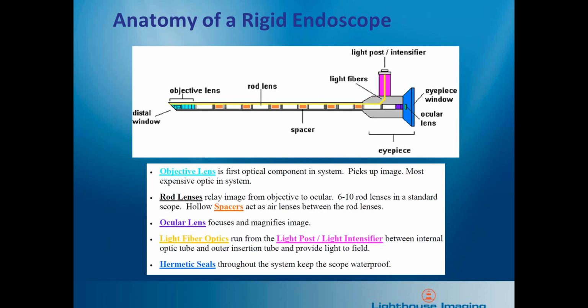So we'll see in the upper image here, starting at the left end of what's shown here, what would be typical for an arthroscope. We'll see the distal window, and then we'll have an objective lens assembly, which you could most typically think of as being like a camera lens. So that creates the image. And then inside of these rigid endoscopes are typically a series of rod lenses. This is a long, skinny piece of glass that transfers the image along the shaft of the endoscope. So in between these rod lenses would be hollow tube spacers. And then at the right end, or the proximal end, would again be this ocular lens and the eyepiece window to present the image to the user or to a camera clipped to the endoscope.